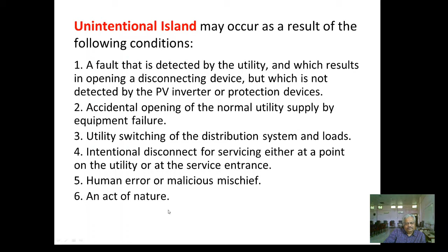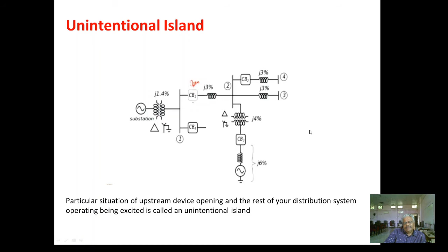Now, this is shown here again: unintentional island due to opening of the circuit breaker. An unintentional island is formed. A particular upstream device opens, and the rest of your distribution system remains operating and energized. This is called an unintentional island. I think up to this point, we are clear about what an unintentional island is. Next, we'll see what the issues with an unintentional island are.